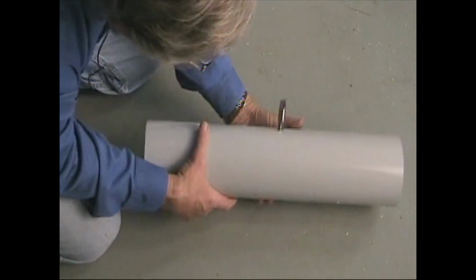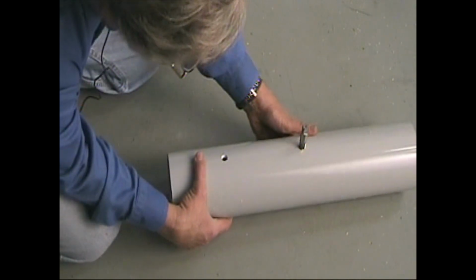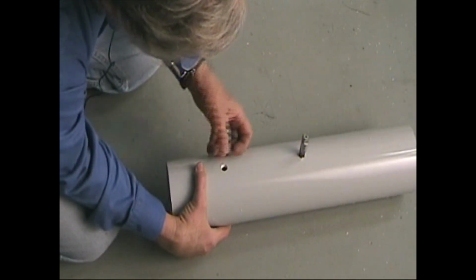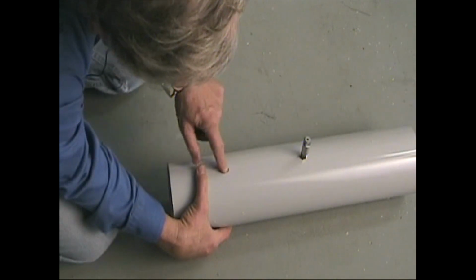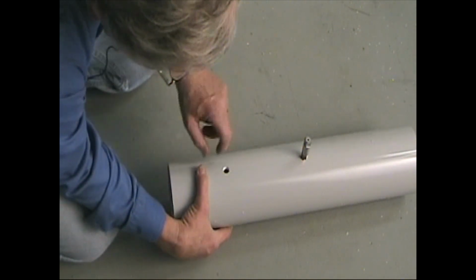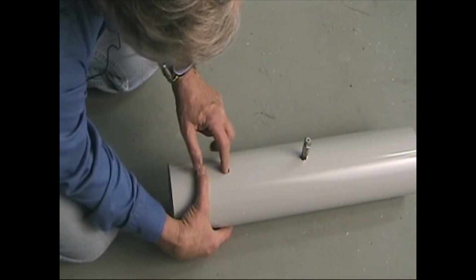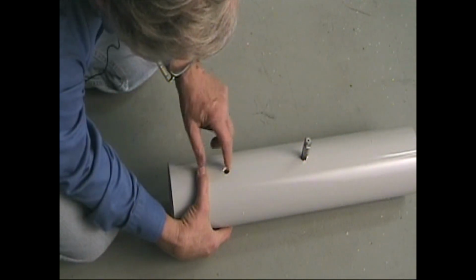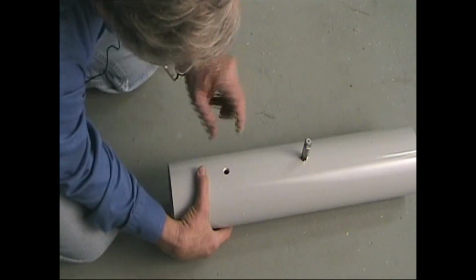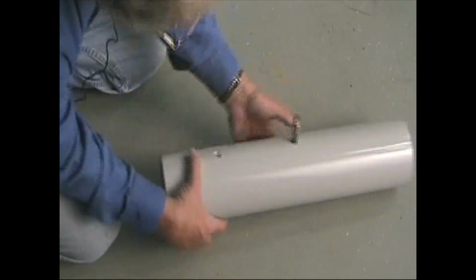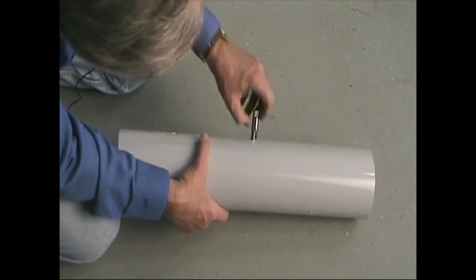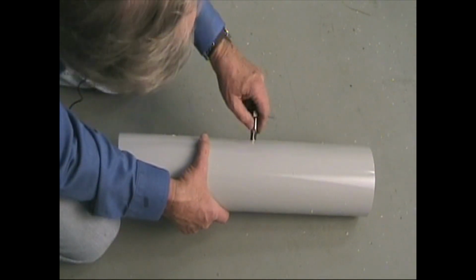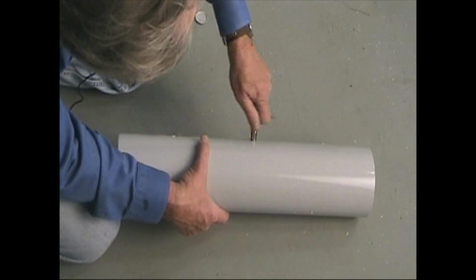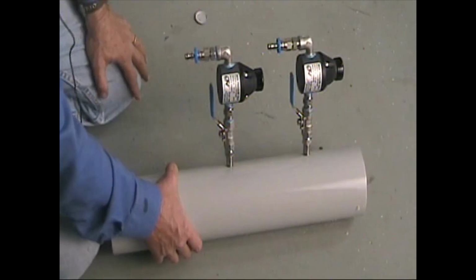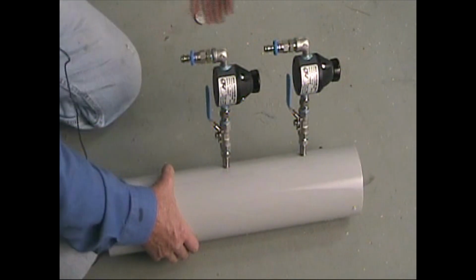Okay. The way you can install the injection lance in the pipe is you're going to use the drill and tap that we supply, drill the hole into your pipe. Use a 1/4 inch as a pilot hole first so that you're not using the full size 7/16. Drill it, then you tap it, and you don't tap it all the way to the bottom. You leave almost about a 1/2 inch out because it's a tapered thread. Finished, it should look like this.